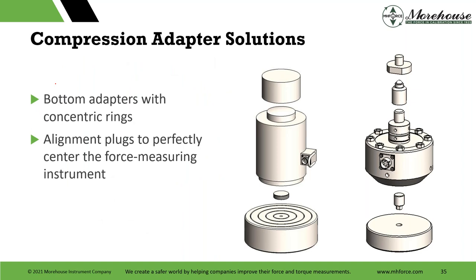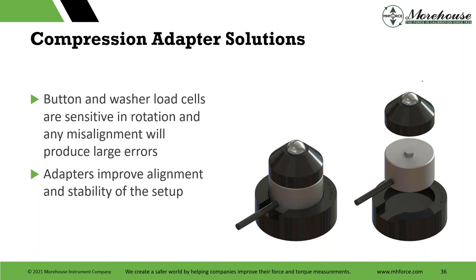And then you have compression adapters and different alignments. If you're in a Cal machine that's under 100,000, this is the recommended adapter. This particular ball adapter and setup, when I did the initial test comparing what we used to sell back in the early 2000s to what we made around 2010, improved the overall reproducibility of the measurement, one of the huge sources of error, or ASTM lower limit factor, by over 30%. So it basically cut a third off a big portion of the uncertainty. Sometimes a half, but I'm more comfortable saying a third.